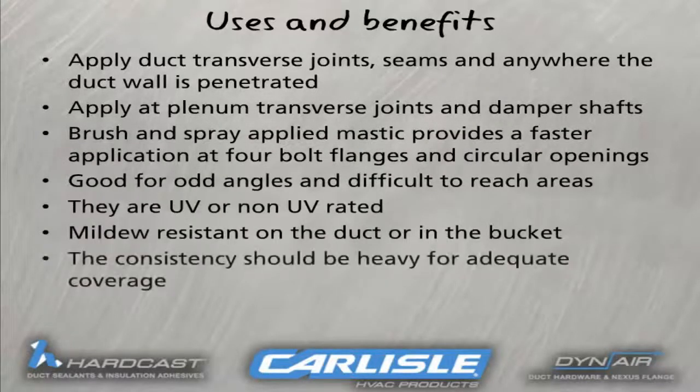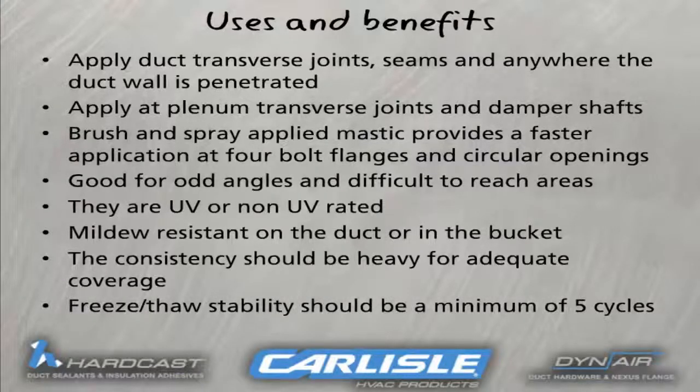These are the major advantages of using either the brush, spray, or caulk applied sealants. Underwriters Laboratory requires that the sealant pass five freeze-thaw cycles and is resistant to mold and mildew. You would apply at duct transverse joints, seams, and anywhere the duct wall is penetrated. Apply at the plenum transverse joints and damper shafts. Brush and spray applied mastic provides a faster application at four bolt flanges and circular openings. Brush, spray, and caulk applied sealants are good for use on odd angles and difficult to reach areas. They are both UV and non-UV rated, both mildew resistant on the duct or in the bucket, and are consistently heavy for adequate coverage. Freeze and thaw stability should be a minimum of five cycles.